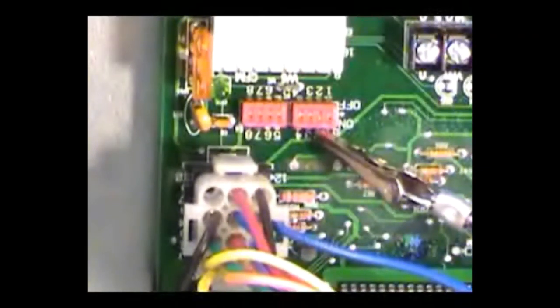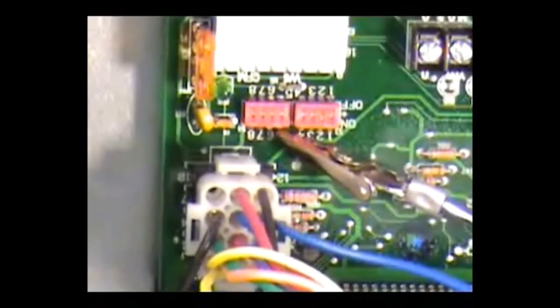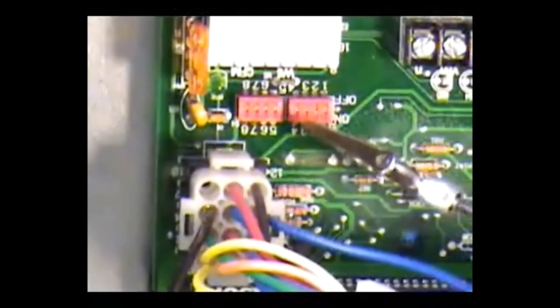All right, every manufacturer is going to have dip switches of some type, like these on this board here, and they will be set from the manufacturer for specific speeds. They are typically done in pairs. One pair is going to actually set your heating speeds. One pair will typically set your cooling speeds. Okay, third pair is a delay pair. That pair will determine the characteristics of how the motor speeds up and slows down at the beginning of the cycle and at the end of the cycle.